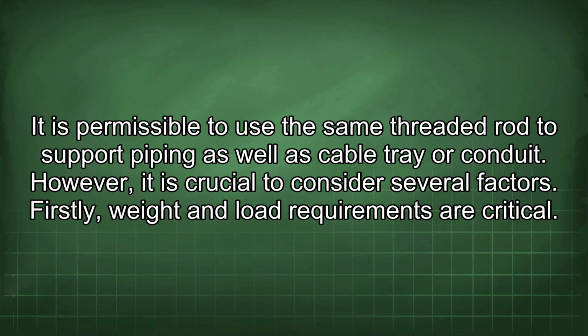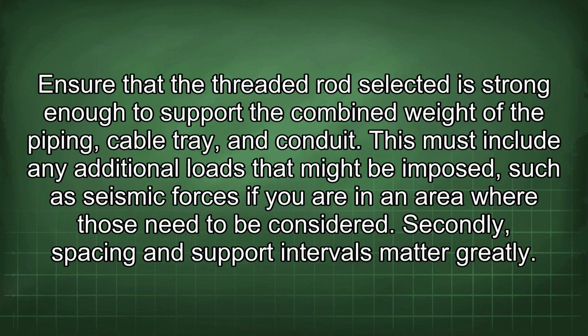It is permissible to use the same threaded rod to support piping as well as cable tray or conduit. However, it is crucial to consider several factors. Firstly, weight and load requirements are critical. Ensure that the threaded rod selected is strong enough to support the combined weight of the piping, cable tray, and conduit. This must include any additional loads that might be imposed, such as seismic forces if you are in an area where those need to be considered.